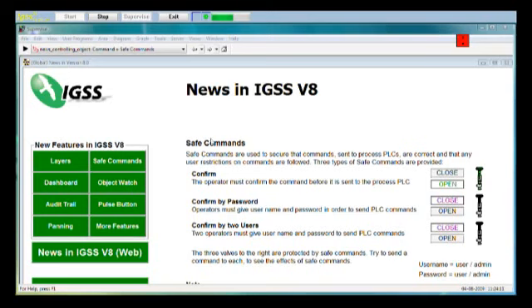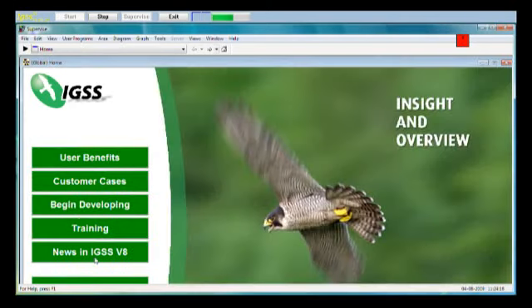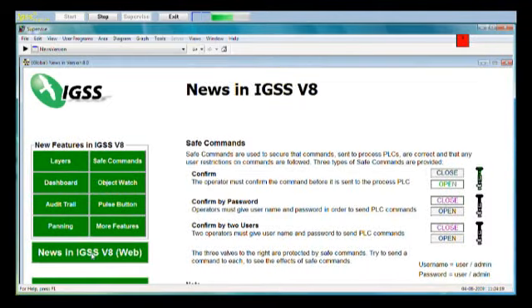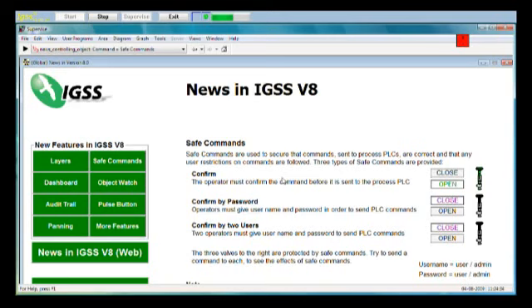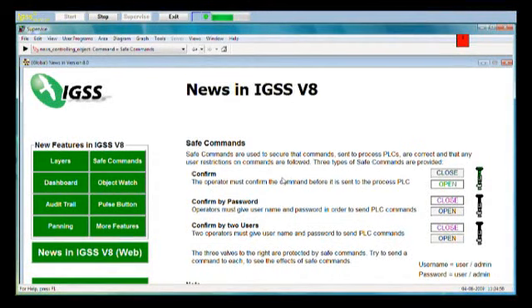We have three different Safe Commands. We are now in the Supervise module, and if you go to the first page of our demo configuration you have the button news in version 8. When you go in there you can click on Safe Commands to see this picture. We have first of all confirm, which is a simple confirmation dialog box that comes up so that the operator must press OK to carry out a command. Then we have confirm by password, where the user must enter a username and password, and finally confirm by two users, where one user carries out the command and the next user must approve the operation. Of course, the two latter require that user administration is enabled, and that's why we also go into the user administration module.